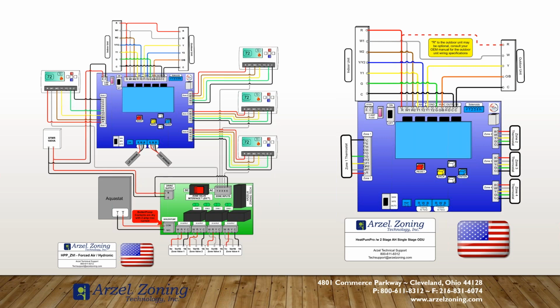So now if you don't want to run through the house and find every single thermostat, or worry about your customer over conditioning in one zone and turning that thermostat off on you, you can disable the solenoids by disconnecting the plus wires and then do your checkup, do your startup, get all your test data, and then reconnect those plus wires and the system will go back to normal operation.